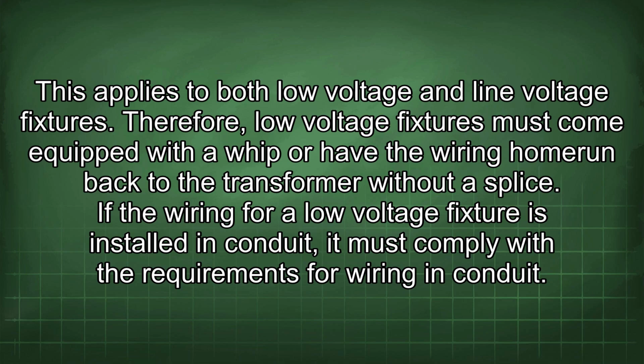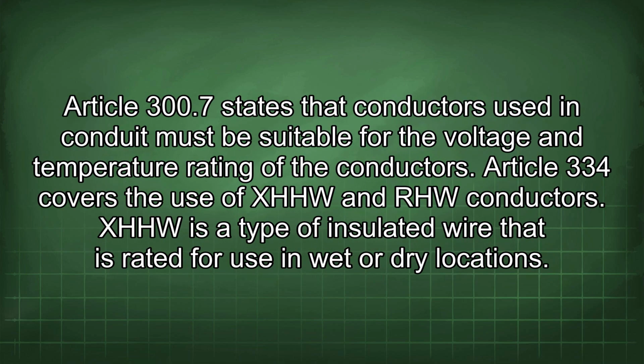Therefore, low voltage fixtures must come equipped with a whip or have the wiring home run back to the transformer without a splice. If the wiring for a low voltage fixture is installed in conduit, it must comply with the requirements for wiring in conduit. Article 300.7 states that conductors used in conduit must be suitable for the voltage and temperature rating of the conductors.